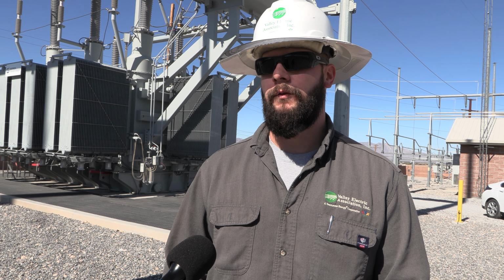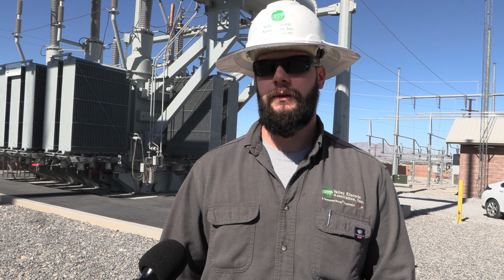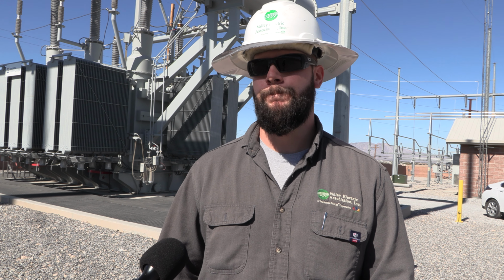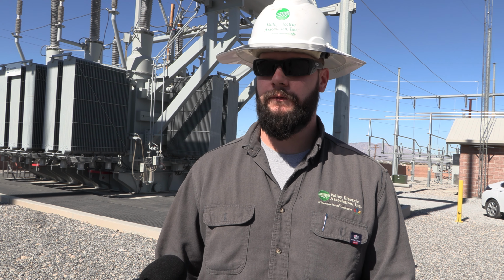So from there, it'll go to a distribution substation at the 138,000 volts where it gets stepped down to the distribution voltage of 24.9. And that's what you see on the power lines all around town. And then pretty much every house has another transformer that puts it down to secondary voltage. So it'll take that 24.9 phase to phase or 14.4 phase to ground and put it to the 120/240, which is what is used inside the houses.